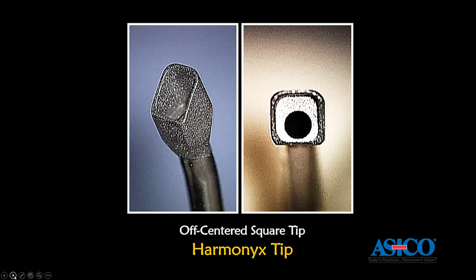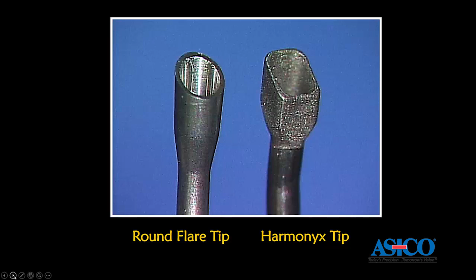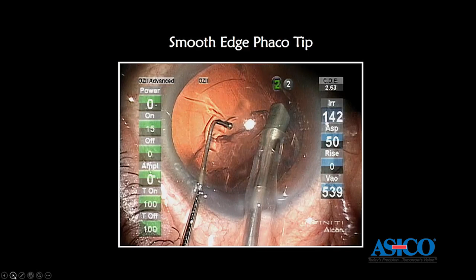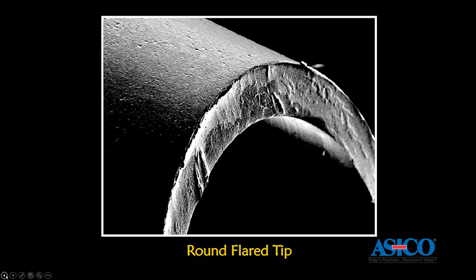This is a square off-centered tip, Harmonyx. As you see, the tip shaft is off-centered to the aspiration port, and the edge is rounded and sandblasted. Compared with the conventional round flare tip, the edge of the tip is smooth, and also the surface is sandblasted. Please look at this video. I aspirate the posterior capsule by accident, and the vacuum is more than 500, but the posterior capsule didn't rupture. Now 390, but the capsule doesn't rupture.